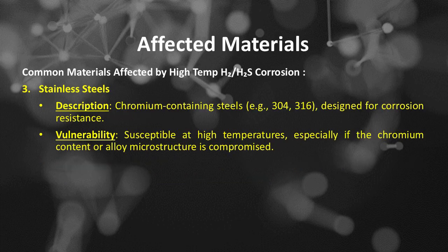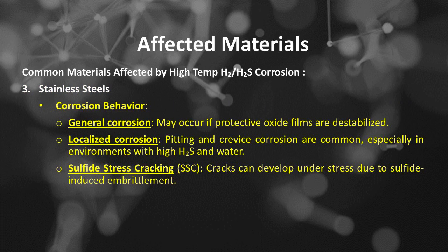The affected materials, number 3, is stainless steels. Chromium-containing steels, such as 304, 316, designed for corrosion resistance. The vulnerability of the stainless steels: susceptible at high temperatures, especially if the chromium content or alloy microstructure is compromised. The corrosion behavior of high-temperature hydrogen or H2 and hydrogen sulfide or H₂S corrosion on these stainless steels includes general corrosion, which may occur if protective oxide films are destabilized; localized corrosion, where pitting and crevice corrosion are common, especially in environments with high hydrogen sulfide or H₂S and water; and sulfide stress cracking or SSC. Cracks can develop under stress due to sulfide-induced embrittlement.